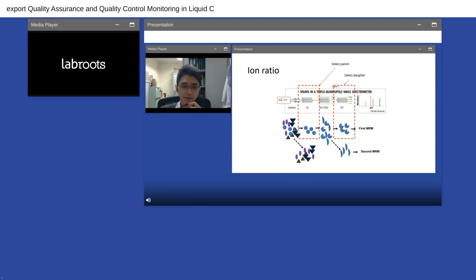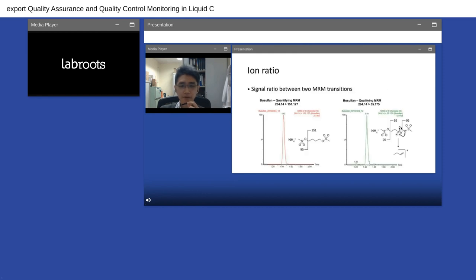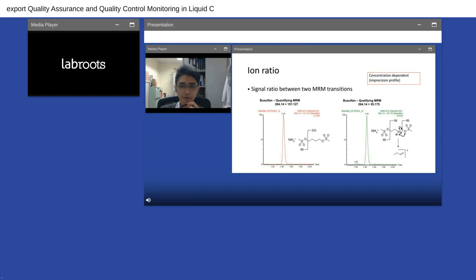For a triple quad assay, we measure the analyte based on Q1 and Q3 mass channels. We select the parent on Q1 and the daughter on Q3 — the parent-daughter pair is called the MRM channel. For measurement of an analyte, we typically measure two MRM transitions. The ion ratio is the signal ratio between the two MRM transitions — essentially measuring two different fragments from the same parent molecule. If the molecule is correct and detection is specific, the ion ratio should be quite consistent across different samples.